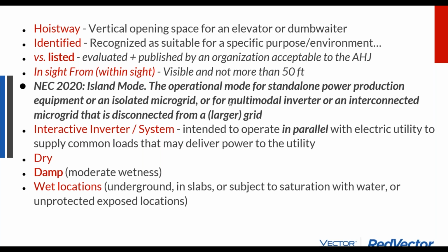Let's see, NEC 2020 defined island mode. Anti-islanding is a term that is a little bit confusing, but basically a microgrid is an island, and then your grid-tied is the regular mode, the non-island mode. And there are some advanced issues on that, of course, that relate to the inverter interactive system. An inverter interactive system is intended to operate in parallel with the electric utility.